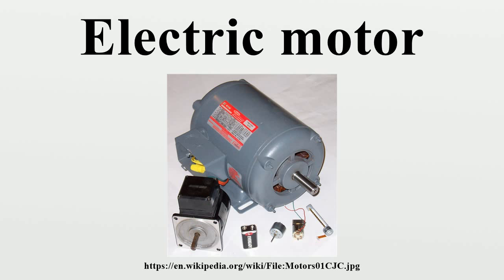The distance between the rotor and stator is the air gap. The air gap has important effects, and is generally as small as possible, as a large gap has a strong negative effect on the performance of an electric motor. It is the main source of the low power factor at which motors operate. The air gap increases magnetizing current. For this purpose, air gaps should be small. Very small gaps may pose mechanical problems in addition to noise and losses.